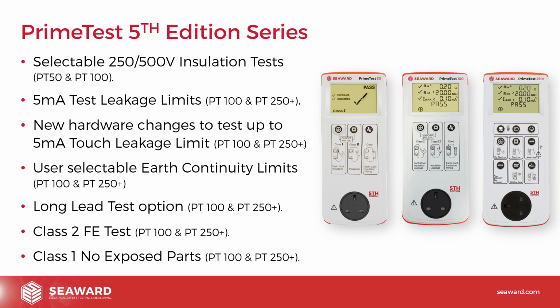So historically we've always had a pass-fail limit of 0.2 ohms, which was obviously higher than the 0.1 plus R specified in the book, and you couldn't change it because it was just preset in the tester. We just picked a good middle of the road value that worked for most people, and that's what we did. Whereas now you've got the ability to select, do you want it as 0.1, 0.2, 0.3, and you can choose that via the settings menu for both the Prime Test 100 and on the 250 Plus.